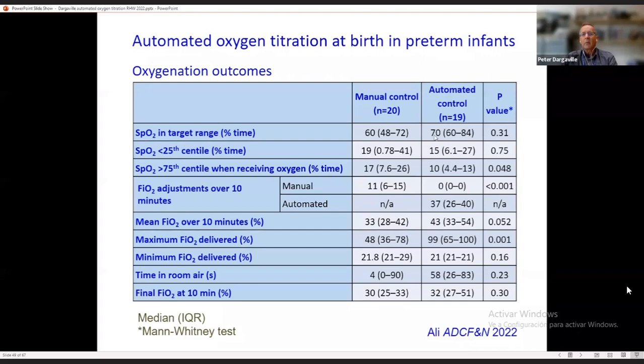It was numerically higher by 10% in the automated control group, but in our small study, this was not a significant result, nor was the time below the 25th centile different. However, the time above the 75th centile when receiving oxygen was somewhat lower in automated control than in manual control. I'll just point out that the clinicians were trying pretty hard to keep the FiO2 in the target range and made 11 adjustments on average during the 10-minute recording to FiO2. The automated control device made 37 adjustments of 1% or more on average over the first 10 minutes.